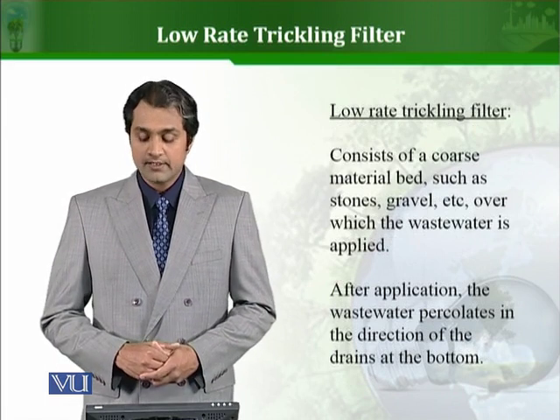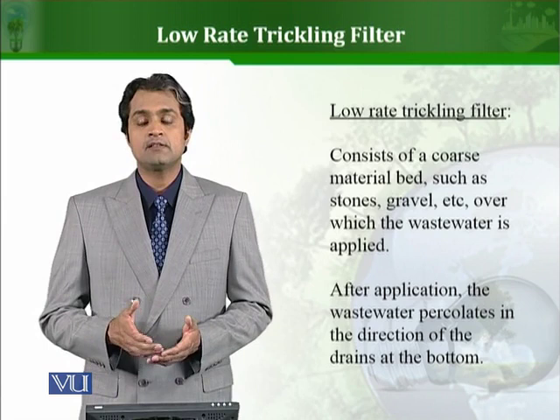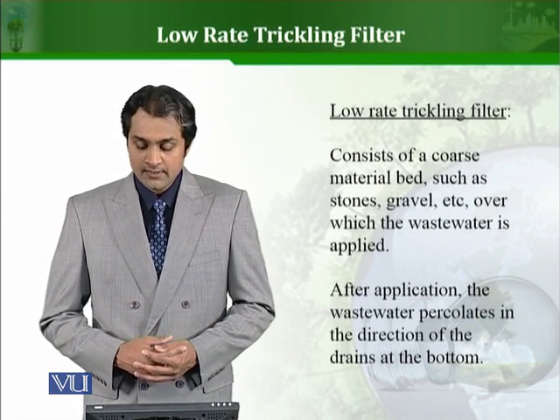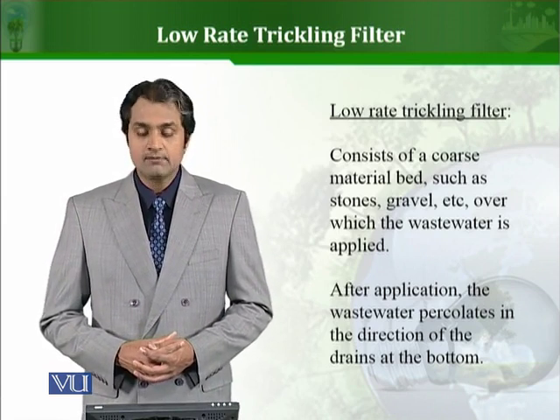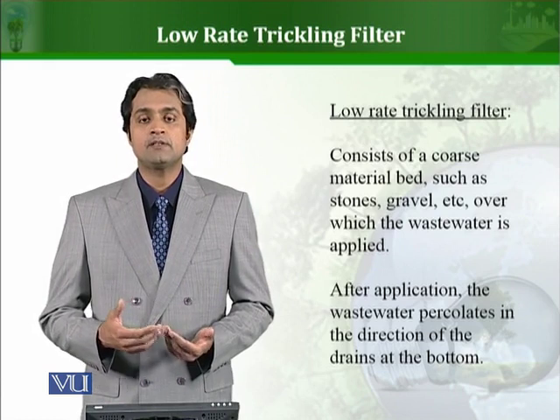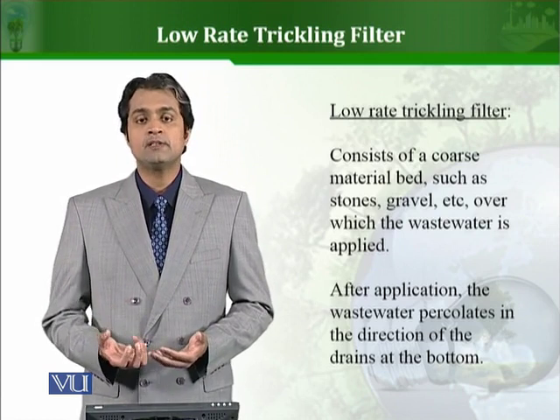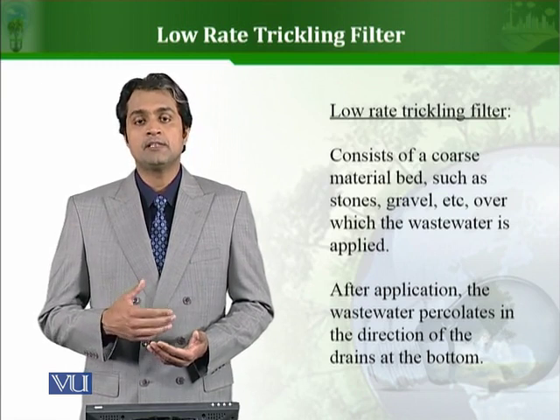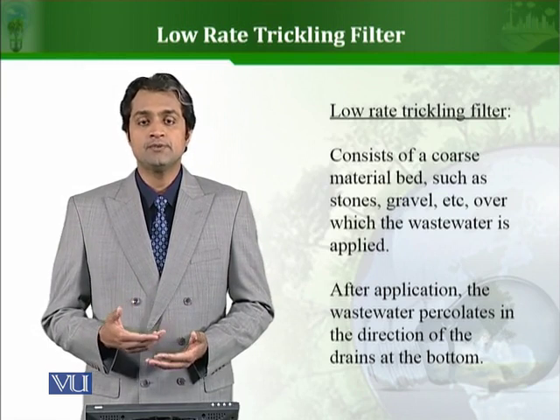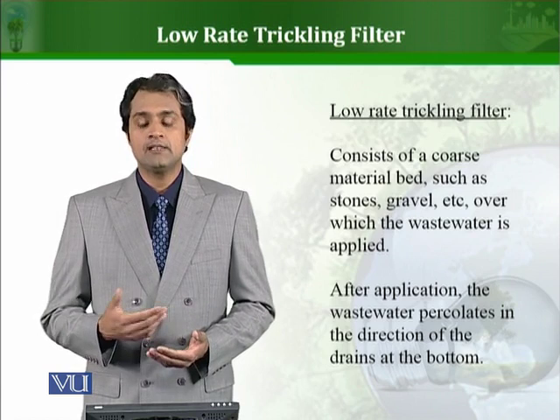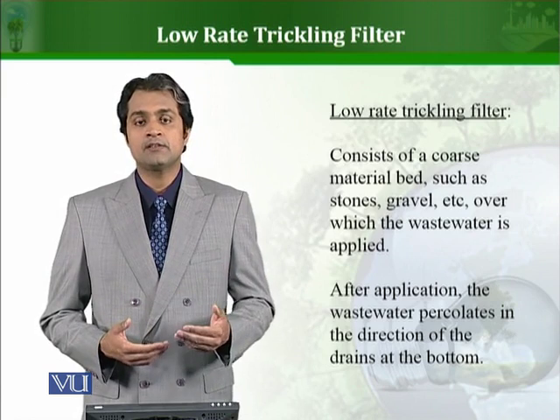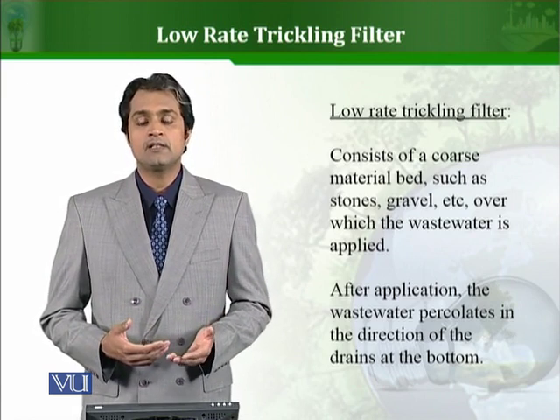Talking about low rate trickling filters — among all aerobic filters, the first type is the low rate trickling filter. It consists of a coarse material bed such as stone, gravel, etc., onto which wastewater is applied. The wastewater contains different microorganisms which grow on the support material in the form of biofilms. The organic content present in the wastewater serves as food for these microorganisms, so they grow and degrade the organic content.